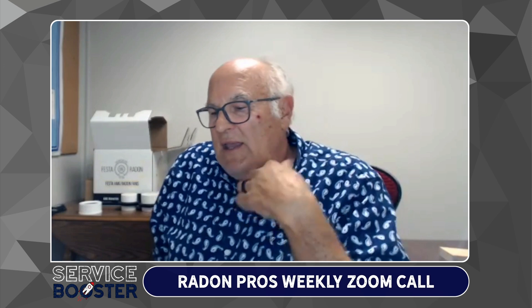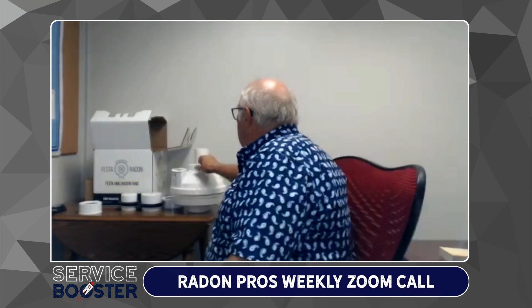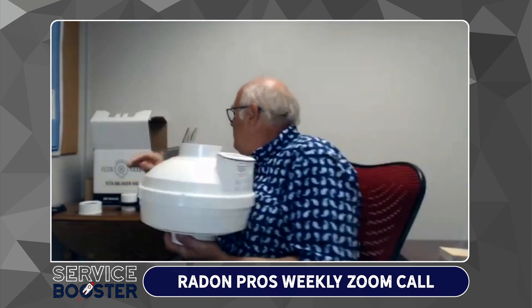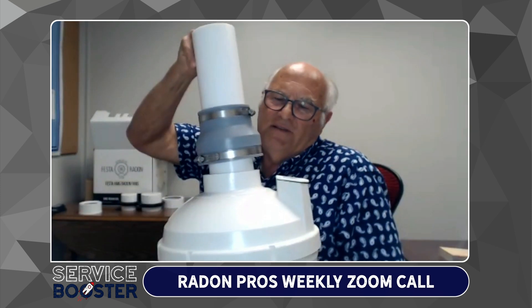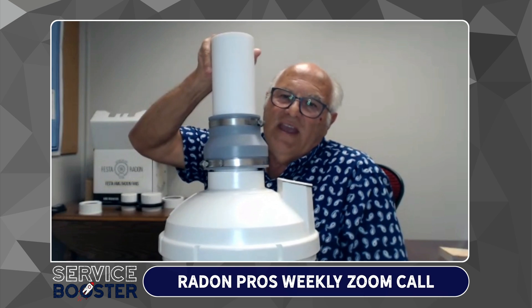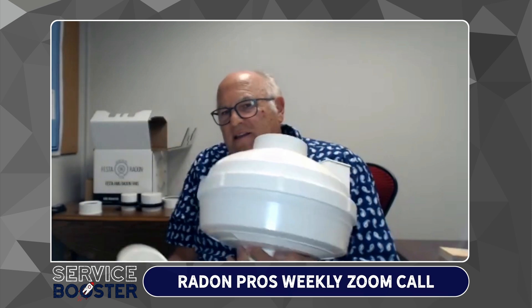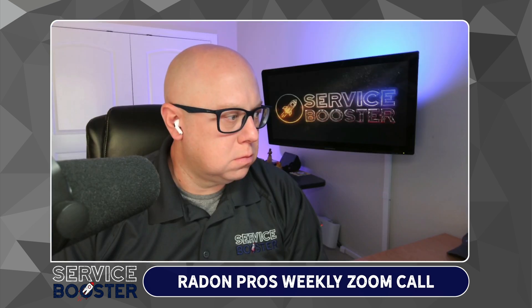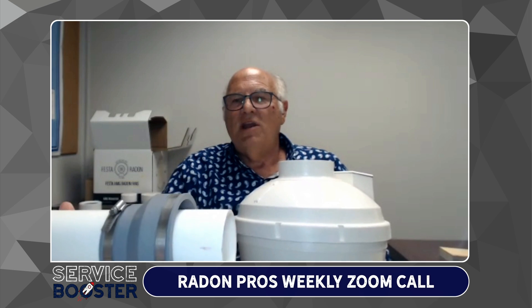We were always good about leveling, bad about PVC glue, and I think there were a few times I was sloppy about getting insulation in the pipe. Another thing I've almost done myself: when coming in from the top with your exit pipe, don't let it go too far down in the fan. If it's in the top, it's just going to affect the fan's performance. But if it's coming in the bottom, it's going to scrape the impeller and ruin it.